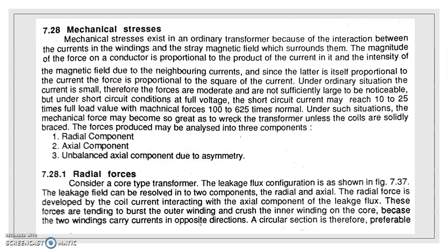If we consider a short circuit condition, the current may reach 10 to 25 times the full load value. As I said, the force is proportional to the square of the current.